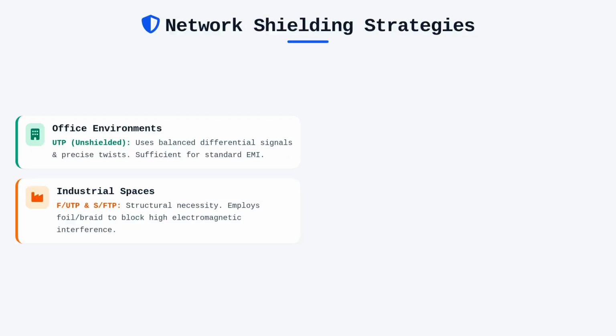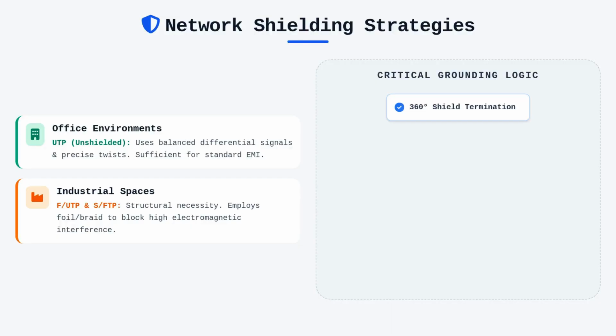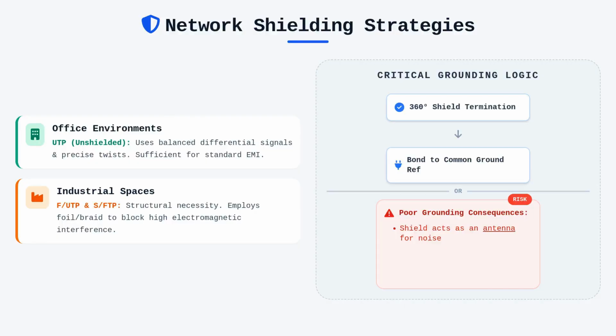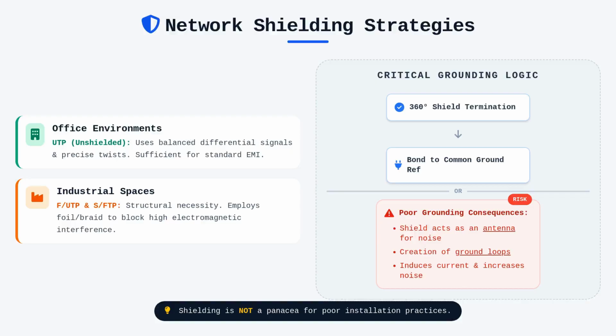However, in industrial spaces or areas with high electromagnetic interference, moving to F/UTP or S/FTP becomes a structural necessity. These constructions involve a foiled or braided shield that must be properly bonded to the grounding system through a high-quality 360-degree shield termination. If the shield is not connected to a common ground reference at the telecommunications bonding backbone, it can act as a giant antenna, capturing common mode noise instead of blocking it. Furthermore, poor grounding creates the risk of ground loops, where multiple potential gradients induce current flow through the shielding, inadvertently creating more noise than the shield was meant to block in the first place.